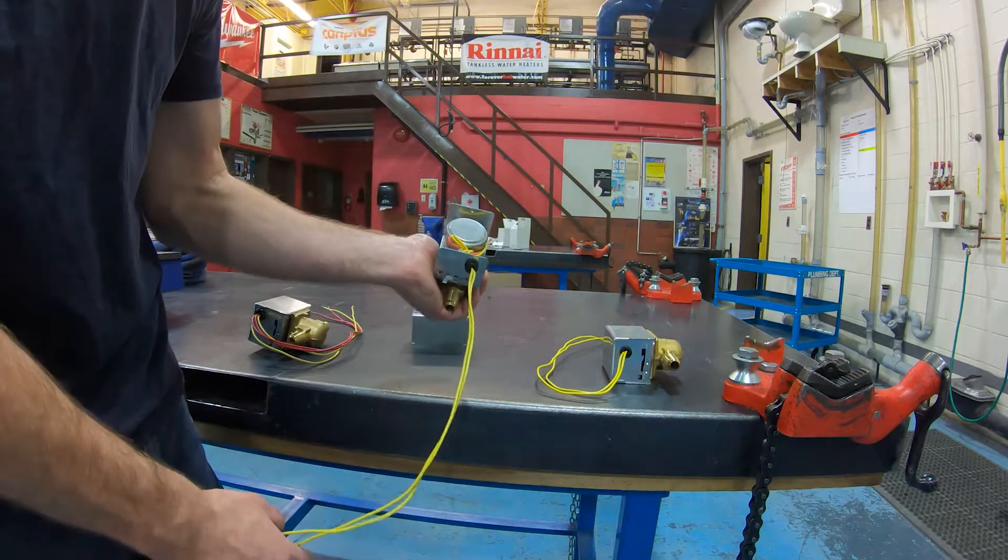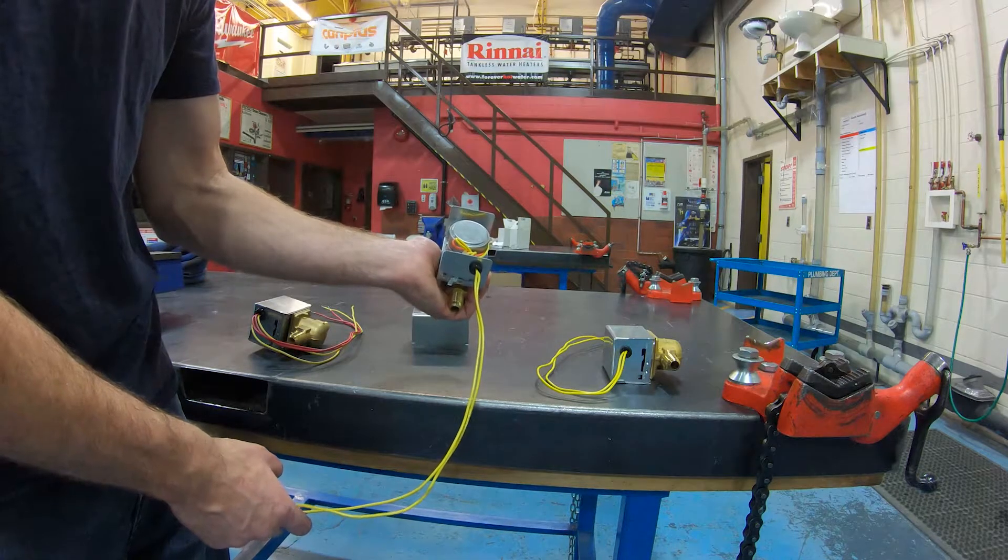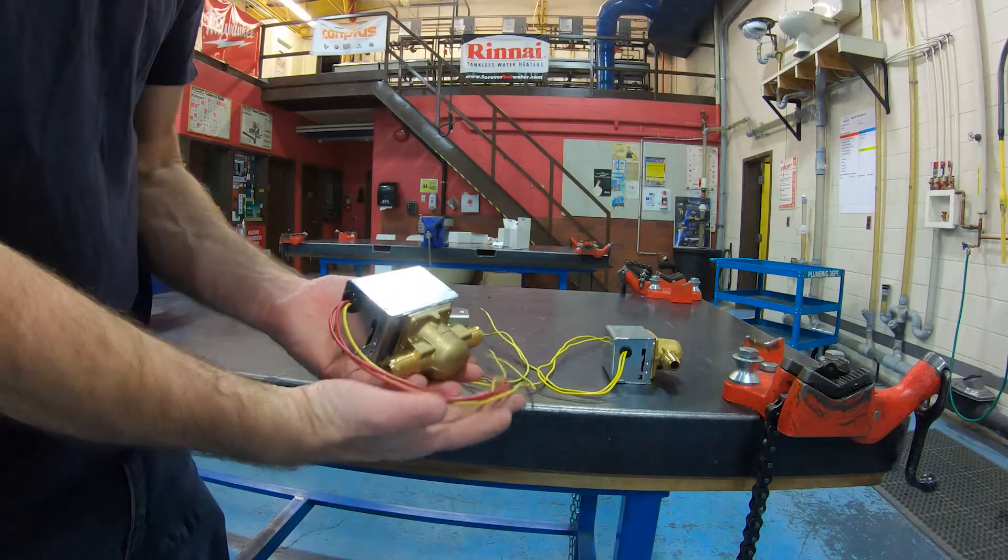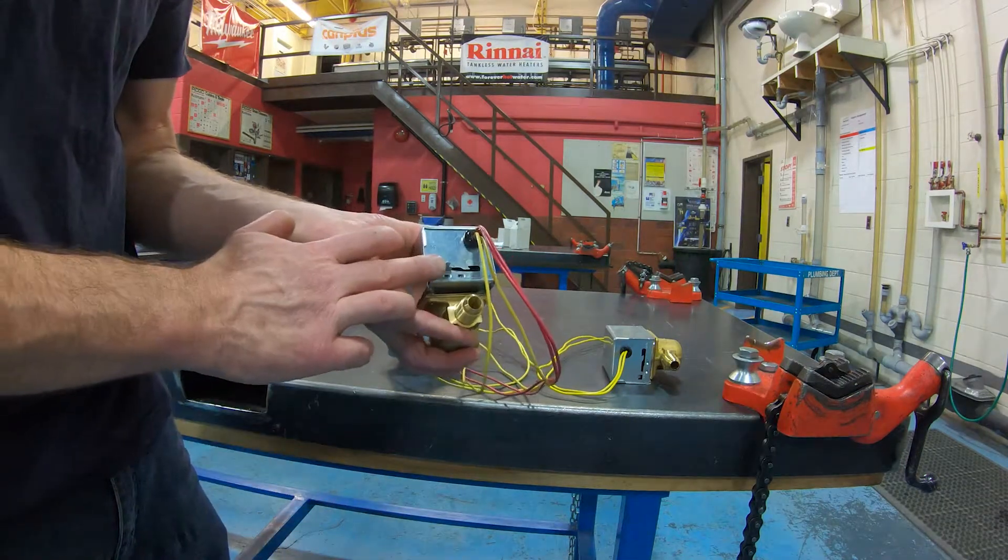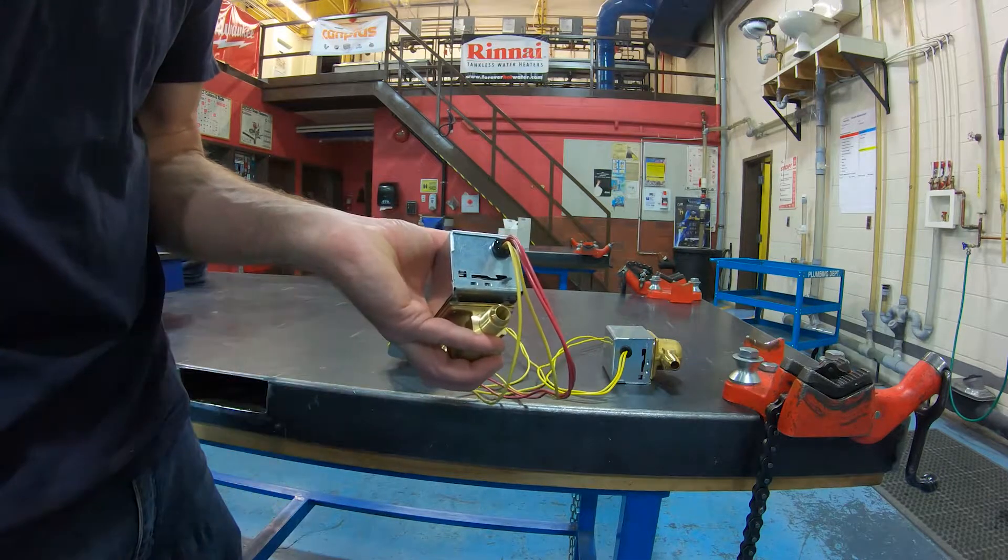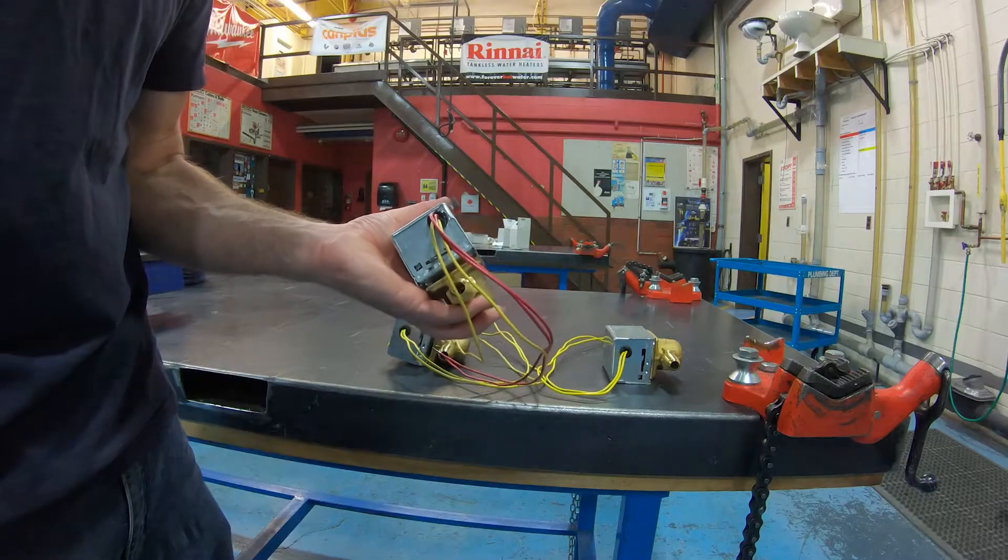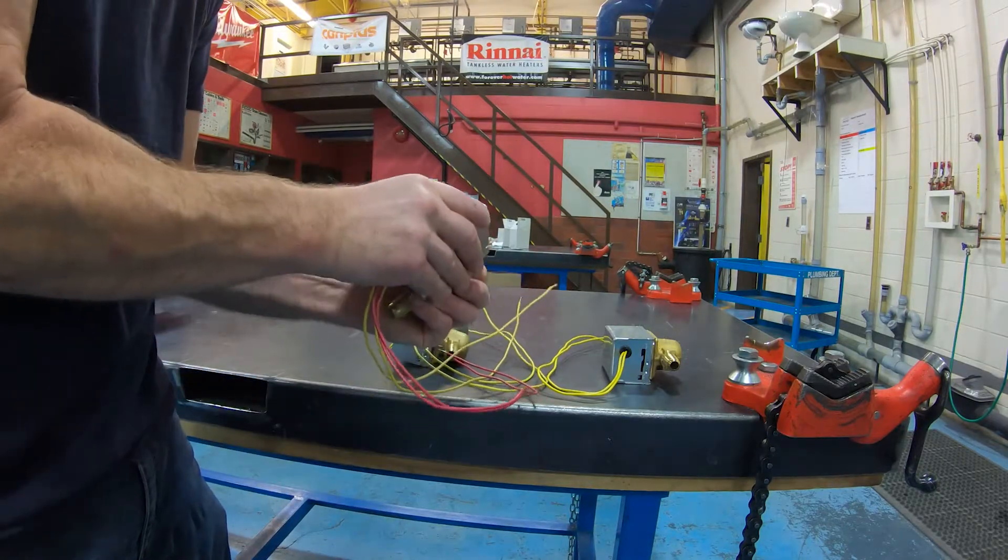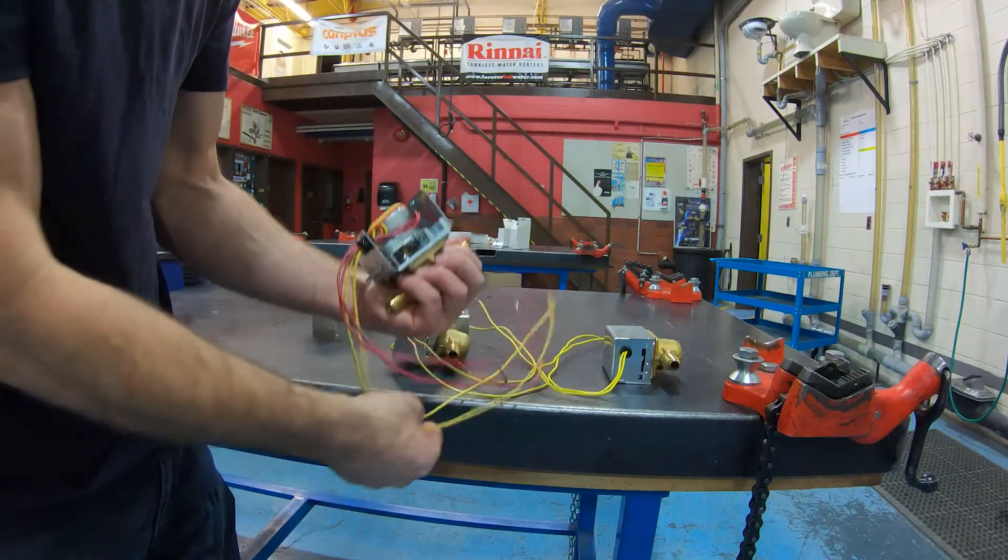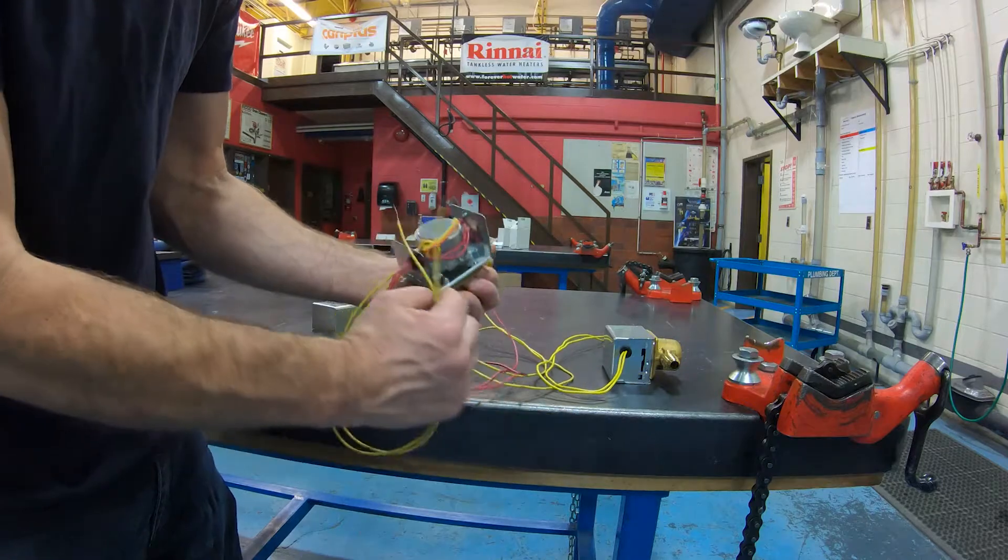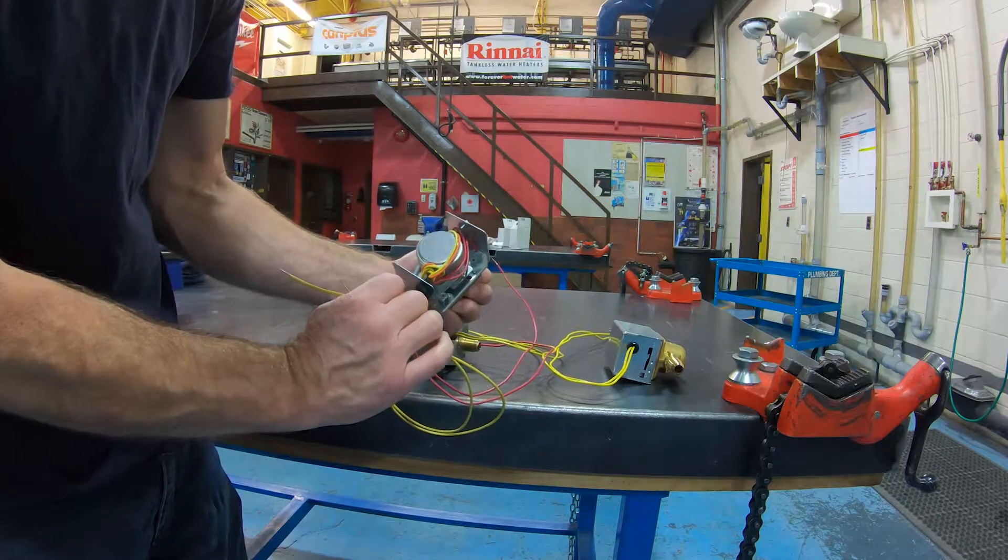So what happens here is when I bring power to the zone valve motor, this actuator with these wires which is 24 volts, it opens up and water flows through. The second type is also a normally closed zone valve and I can also tell that because it does have this manual tab on the side here to manually open it up. Notice how this one has four wires. Two wires, these two yellow ones, go to the actuator motor just like the first one.